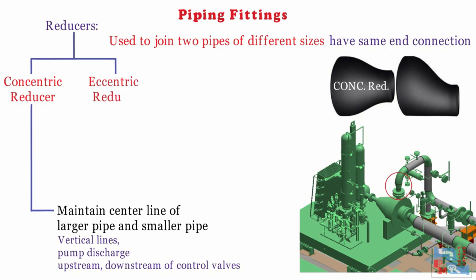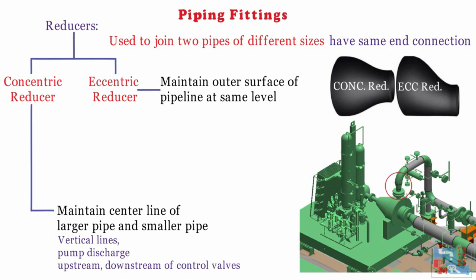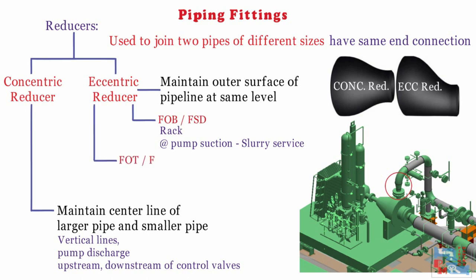Second is eccentric reducer, commonly denoted as ECC reducer in isometrics and P&IDs. It is used when we need to maintain one of the outer surfaces of the pipelines at the same level. Based on orientation, eccentric reducers are further divided as flat on bottom (FOB) or flat side down (FSD), used to maintain the same bottom of pipe elevation in pipe racks and for pumps handling slurry services; and flat on top (FOT) or flat side up (FSU), used to maintain top of pipe at the same elevation and at the suction of pumps to avoid cavitation, and upstream and downstream of control valves.